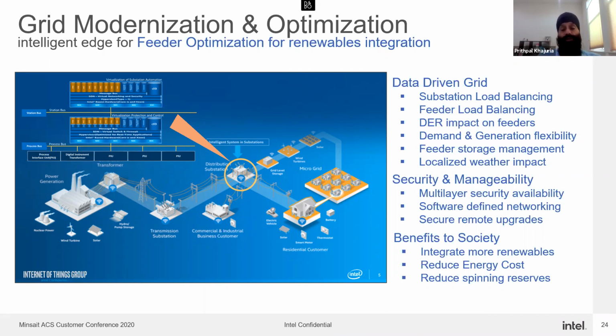When there's too much renewable generation, we let the excess power go into storage, and when the renewables disappear, we can immediately start discharging that storage to balance the feeder. What does this lead to? It leads to a grid of microgrids, where each feeder acts as a microgrid, turning the grid into a data-driven grid.